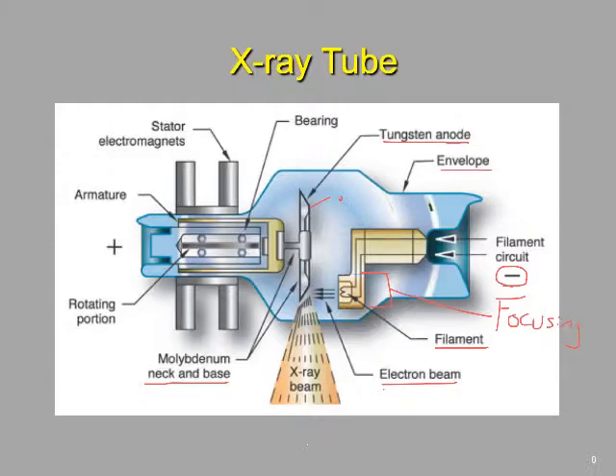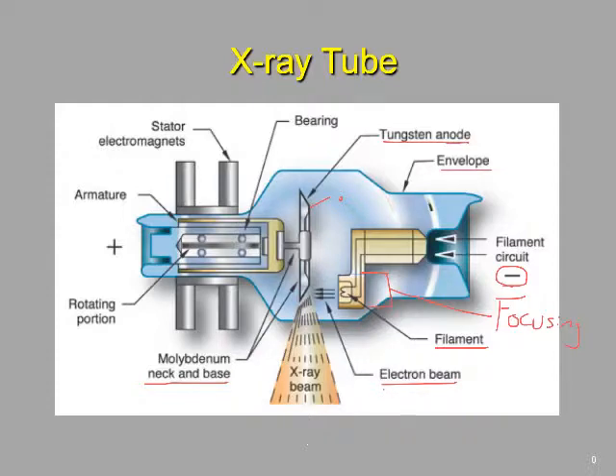That is an electron beam accelerated from the cathode to collide into the anode. In a single second, trillions of electrons are colliding with the anode. A whole lot of x-rays are being produced, but the majority will run into the housing itself. When x-rays are produced, they're produced isotropically — meaning in all directions at the same time — almost like an atomic bomb going off inside this tube with energy going out in all directions.